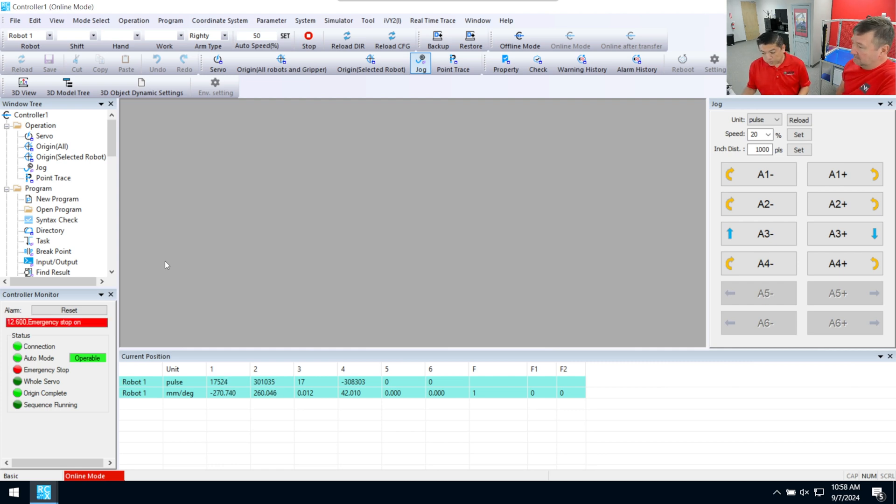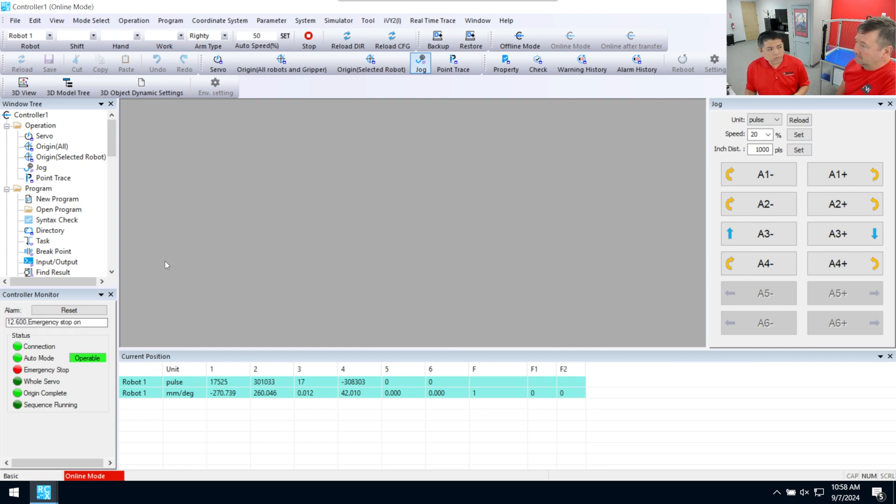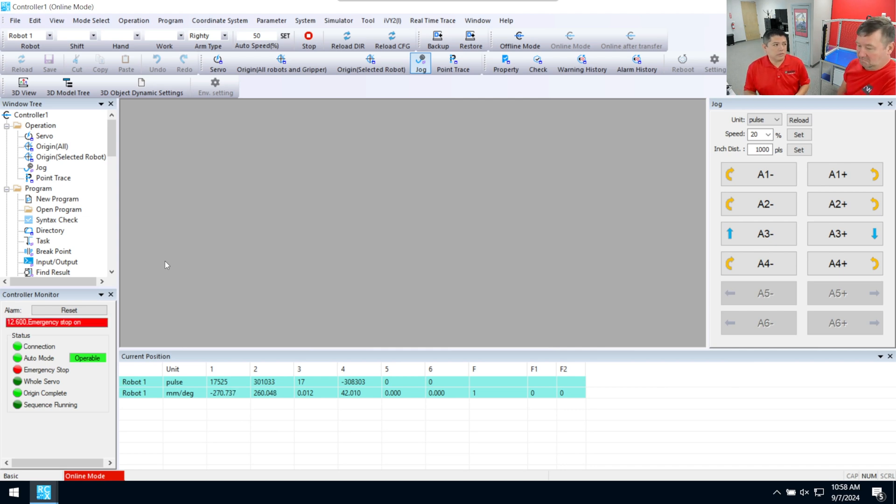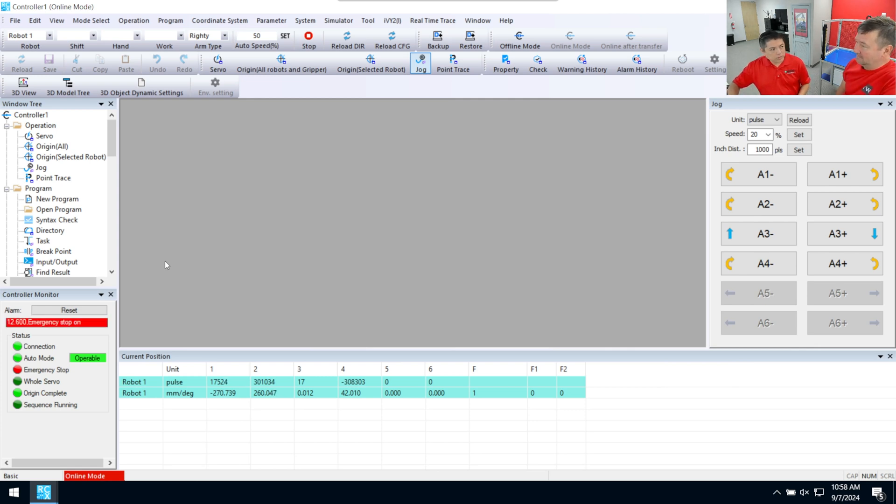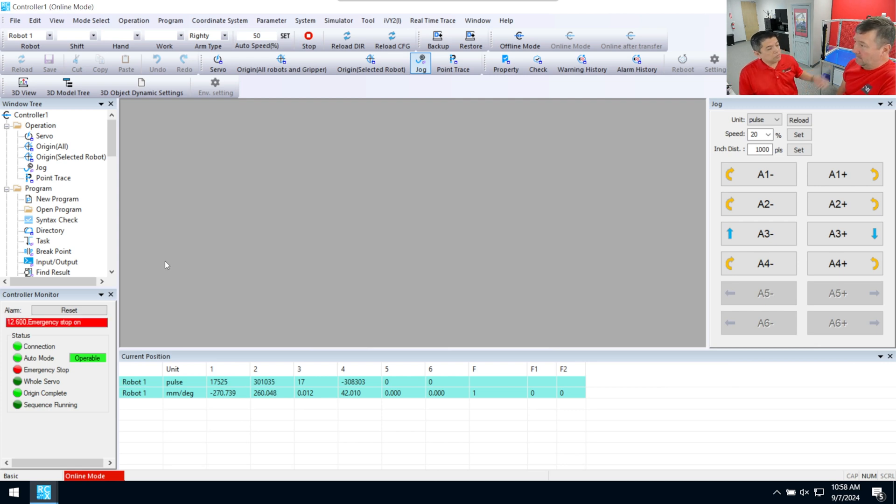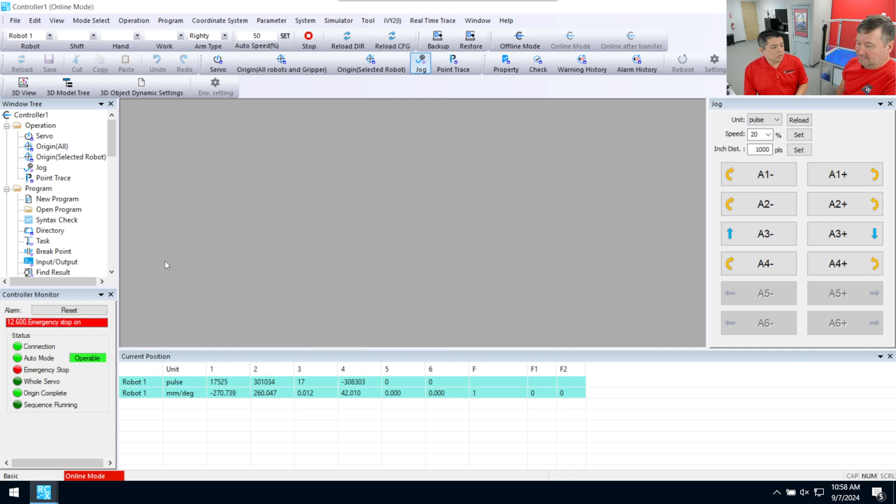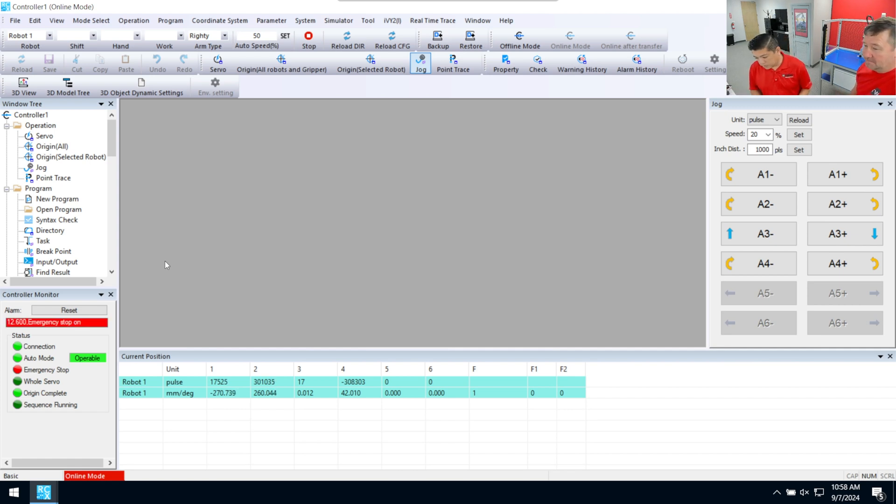So we probably want to, what I recommend is actually starting the robot up without enabling the Ethernet IP. Because once we enable that card, then we're forced to set all of the bits and e-stop bits and all of that. So if we kind of hold off on not setting up Ethernet IP and just leave that card turned off, we can actually turn the servos on, originate, jog the robot, make sure those things work without the PLC being involved at this point. All right. Let's do it.